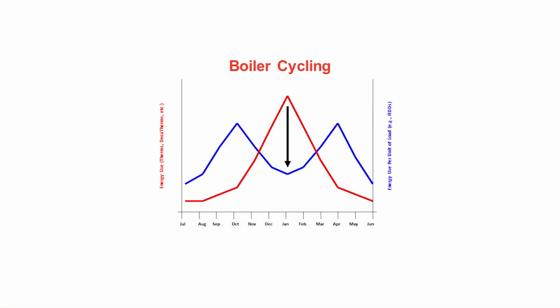Now, it's interesting because if you were analyzing your building and asking, do we really need to replace our boiler plant? It's 20 years old, it's non-condensing, should we replace it? You could look at your bills, how much you spent in gas, the heating degree day hours for the months, and you would probably see something like that blue line. And you'd say, well, the reality is that dip in January, February, that efficiency we can actually hit with our existing boilers. The problem is we cycle, and so we shoot up in the shoulder seasons.